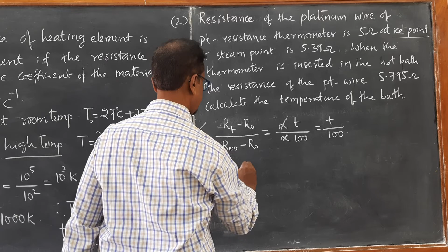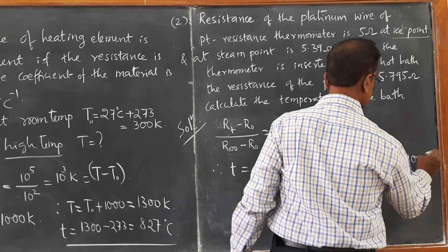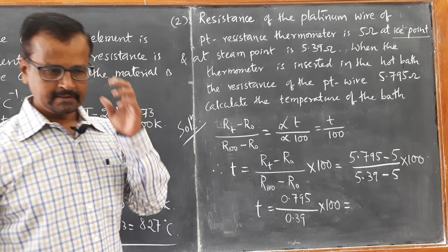So what is RT? The resistance at the higher temperature, 5.795, minus the resistance at 0, this is 5, whole divided by the resistance at 100 degrees Celsius, 5.39, minus the resistance at 0 degrees Celsius, 5. So this multiplied by 100 gives you the temperature in degrees Celsius. 0.795 divided by 0.39 into 100.